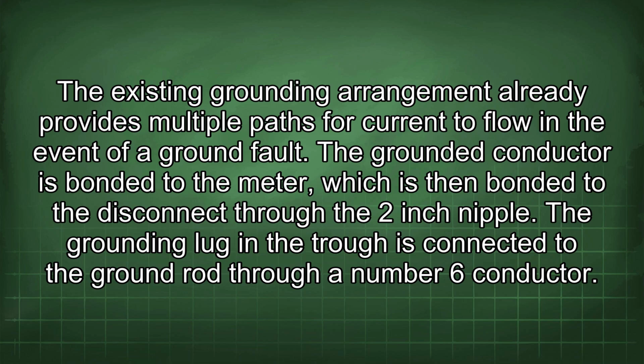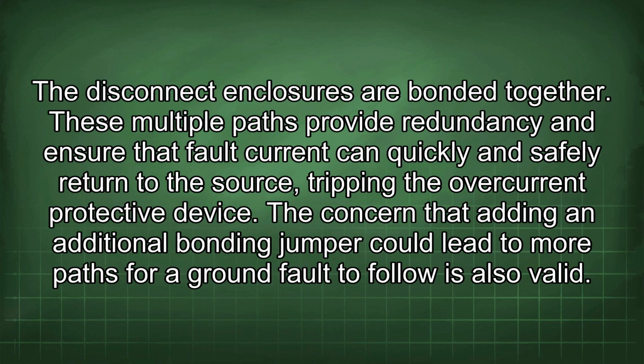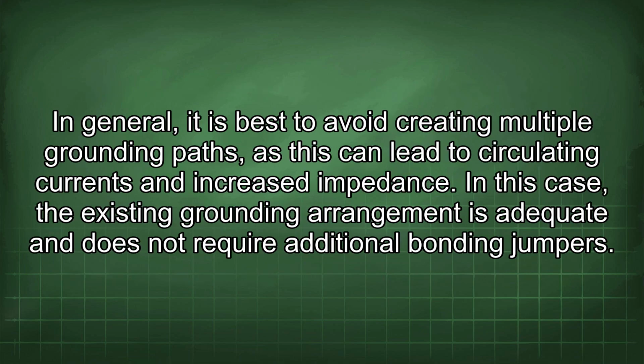The grounding lug in the trough is connected to the ground rod through a number 6 conductor. The disconnect enclosures are bonded together. These multiple paths provide redundancy and ensure that fault current can quickly and safely return to the source, tripping the overcurrent protective device. The concern that adding an additional bonding jumper could lead to more paths for a ground fault to follow is also valid. In general, it is best to avoid creating multiple grounding paths, as this can lead to circulating currents and increased impedance. In this case, the existing grounding arrangement is adequate and does not require additional bonding jumpers.